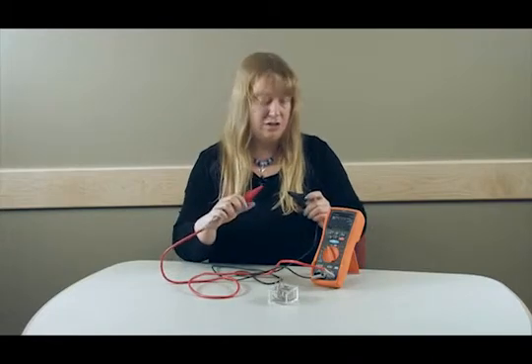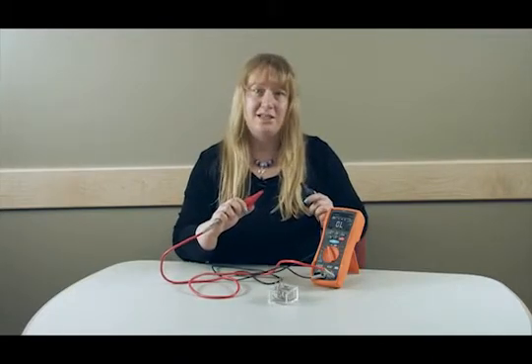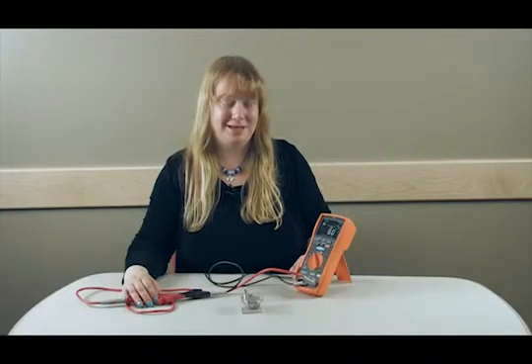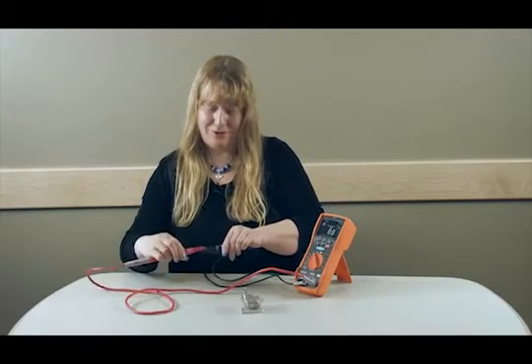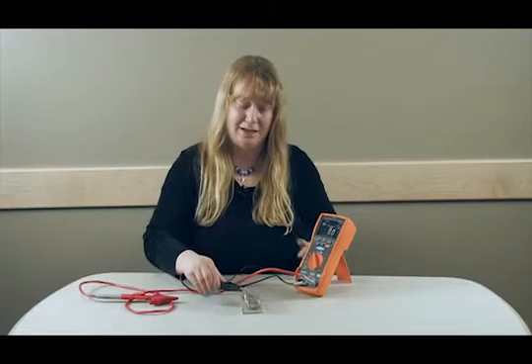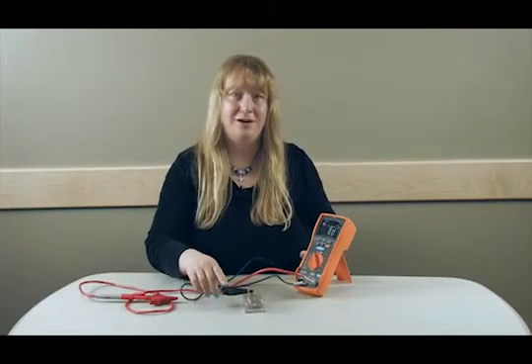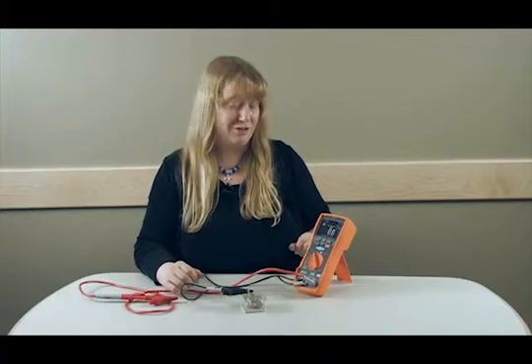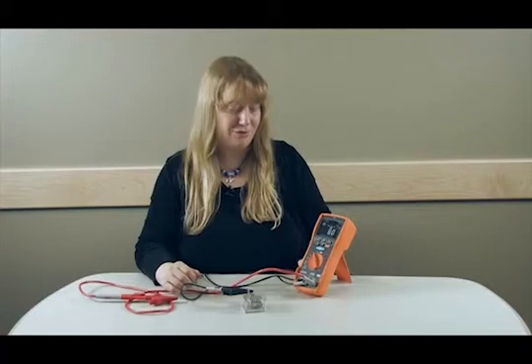The next thing that we are going to want to do is move over to the insulation measurements. Now we're ready to connect to our device under test and make the insulation measurement. First thing that I'm going to do is connect to the low side of our device under test. Another feature to look for in some insulation meters is whether or not it has an earth bond connection test to make sure that you've got a good ground.